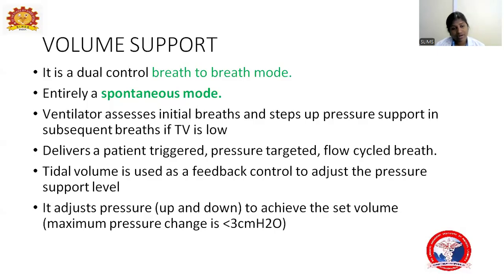And it will deliver a patient triggered, pressure targeted, flow cycled breath. So tidal volume is used as a feedback control to adjust the pressure support level. It adjusts pressure up and down. It can either increase the pressure or decrease the pressure depending on the tidal volume that is delivered by the patient to achieve the set volume. That is, the maximum change will be less than 3 centimeters of water.